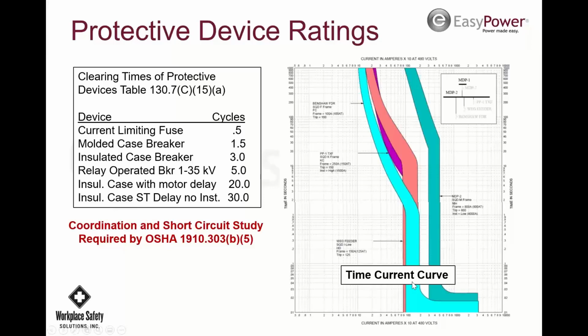But let's go down here. This is now the instantaneous zone. This is very, very fast acting for ground faults and short circuits. And so if a ground fault occurred, so a wire now makes contact with the case and the case shorts out, now the first one that goes is the orange one. That's now the one that is feeding the main distribution. It's coming from main distribution. So this feeds the whole 480 volt panel and 3 other 480 volt panels. So now the motor fault that should take out this breaker takes out 4 separate 480 volt panels.